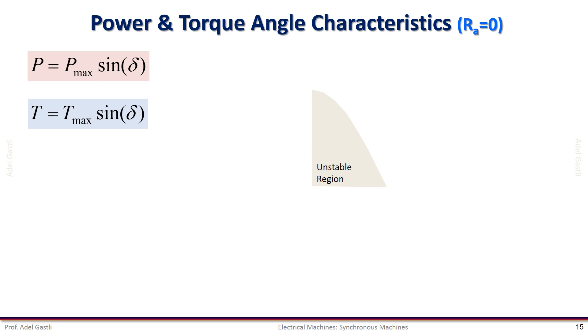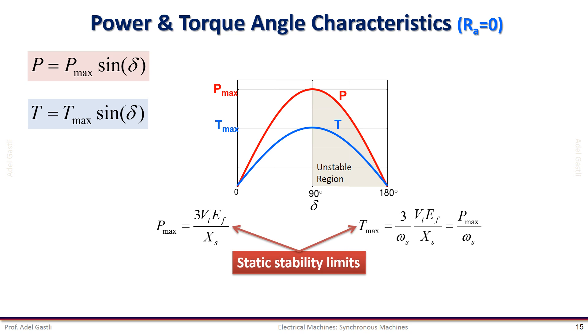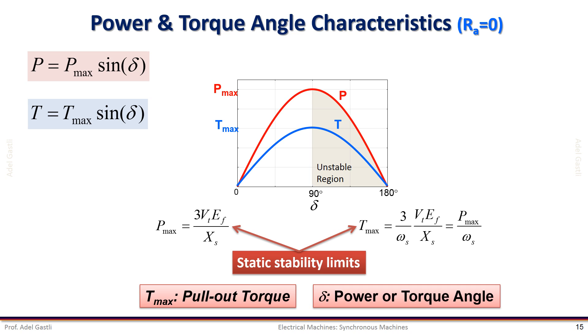These two equations are very important equations describing the power and torque characteristics of a synchronous machine. We can use them to plot the active power and developed torque as a function of the angle delta as given by this figure. Notice that the maximum power and maximum torque occur at an angle delta equal to 90 degrees. Above 90 degrees the machine becomes unstable because the torque produced cannot keep the rotor synchronized with the stator flux — the maximum torque and maximum power are the static stability limits. The maximum torque is called the pull-out torque because above this torque the machine pulls out of synchronism and its speed will decrease to zero. Therefore the angle delta is called the power or torque angle because by controlling this angle we can control the power and torque of the synchronous machine.